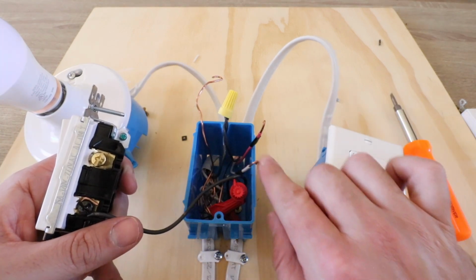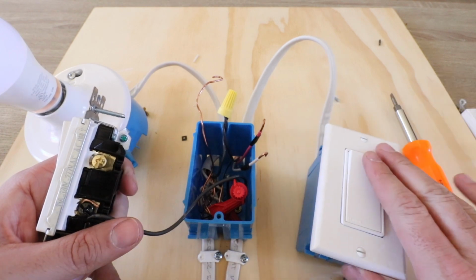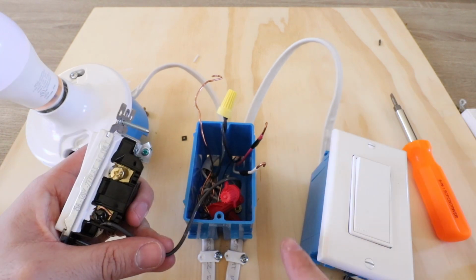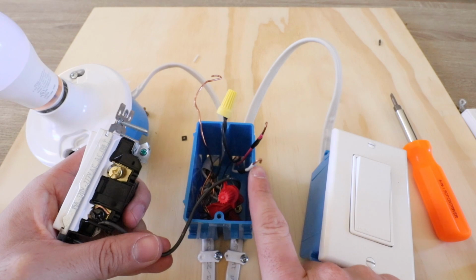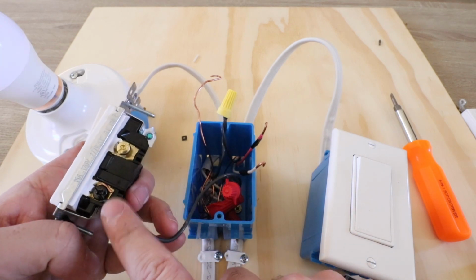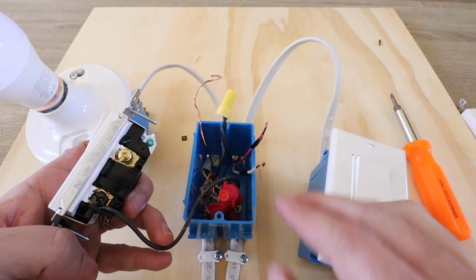Now we need to follow suit with how we wired up the traveler wires in this three-way switch. We're going to put our white traveler wire on the same side as the black wire, just like we did in this three-way switch.